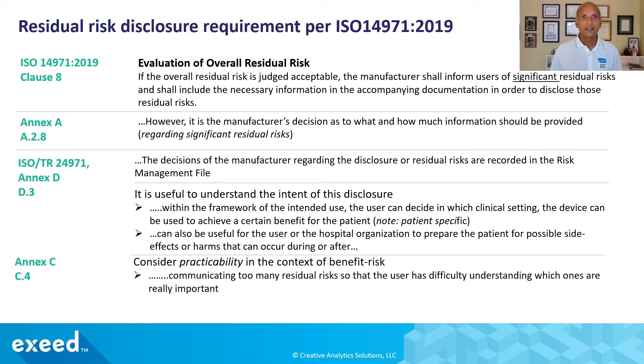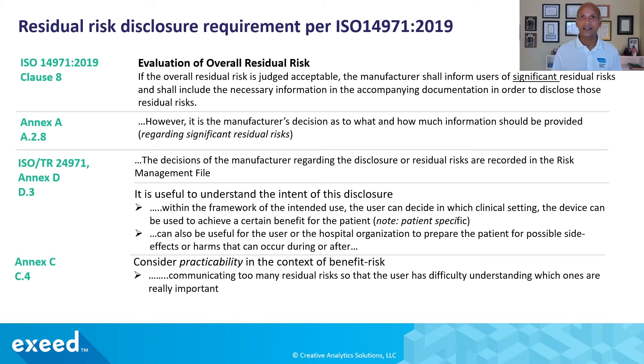Most importantly, in Annex C C.4, consider practicability in the context of benefit-risk. Communicating too many residual risks so that the user has difficulty understanding which ones are really important is not a good thing — you should not be communicating everything. Imagine trying to fly a plane where the dashboard is so complex you cannot understand the signals you are getting and take the right action at the right time. You have to be judicious and smart about what you disclose and how you disclose. That's what ISO is telling you.